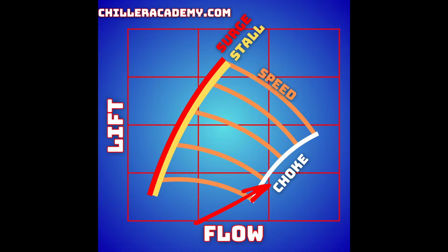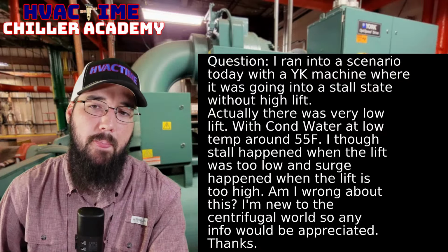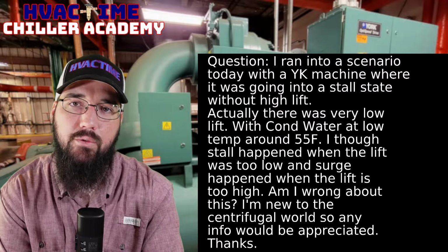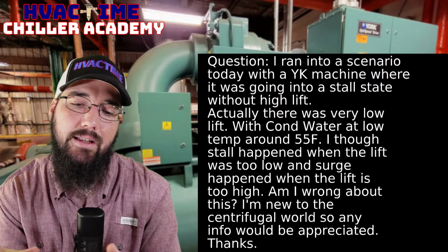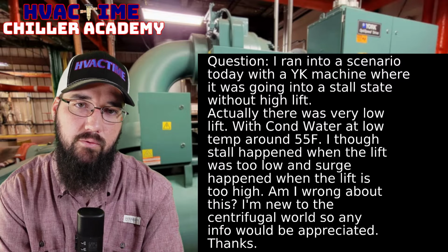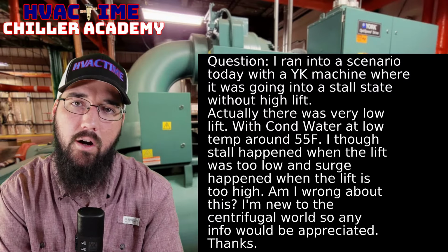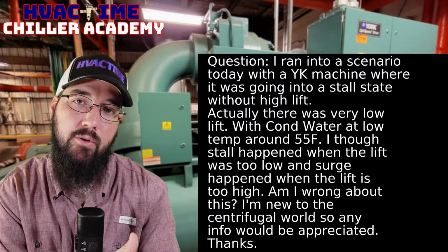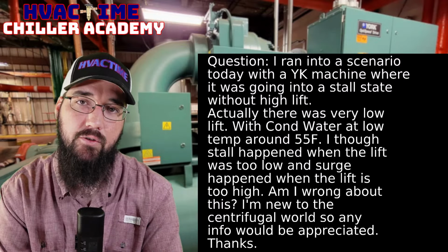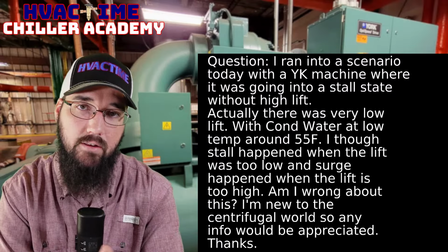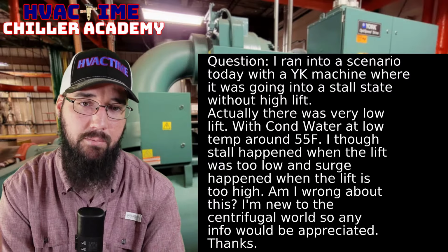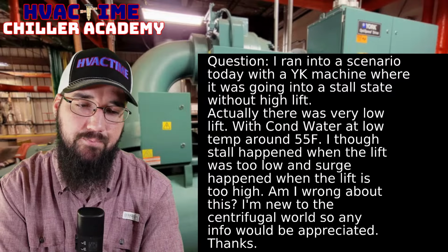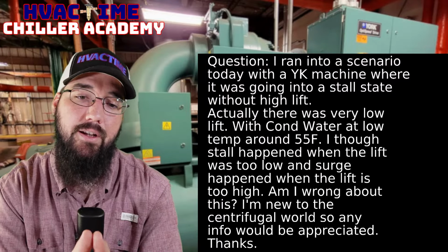Whether you're actually surging or going into a choke is going to depend on how much load you have. Just be aware that what you've done is condenser relief. We can relieve our machine by running really low condenser water temperatures, getting our lift significantly down, which decreases the total horsepower required, or the watts needed, to move the refrigerant from our low pressure saturation to our high pressure saturation. As we reduce the compression ratio, aka the lift, not the same thing but the same kind of concept, we save energy. That's what you've done by going with a 55-degree condenser water temperature.